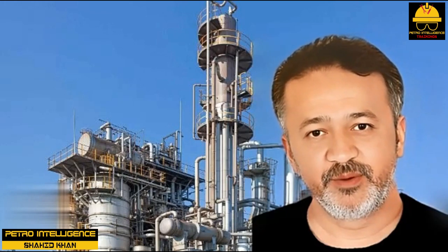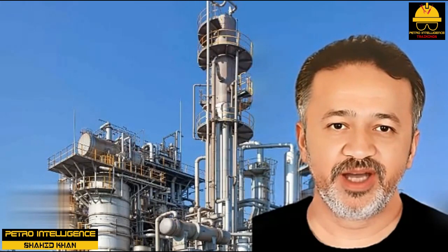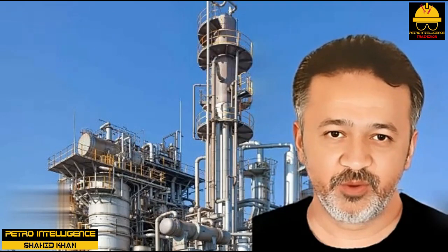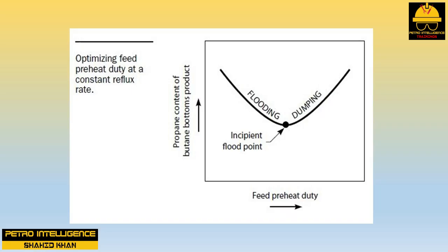Trays suffer from lost efficiency as a result of both flooding and dumping. Trays have some entrained droplets of liquid lifted by the flowing vapors to the trays above — this tends to blow butane up into the lighter propane product. Perforated trays always have some leakage of liquid through the tray deck to the trays below — this tends to drip propane down into the heavier butane product. When we increase feed preheat and the reboiler duty is automatically reduced, dumping increases but entrainment decreases. If the trays below the feed point were flooding, increasing feed preheat would improve fractionation efficiency; if they were dumping, it would reduce efficiency. The feed preheat duty that minimizes the propane content in the butane bottoms product represents the optimum preheater duty.